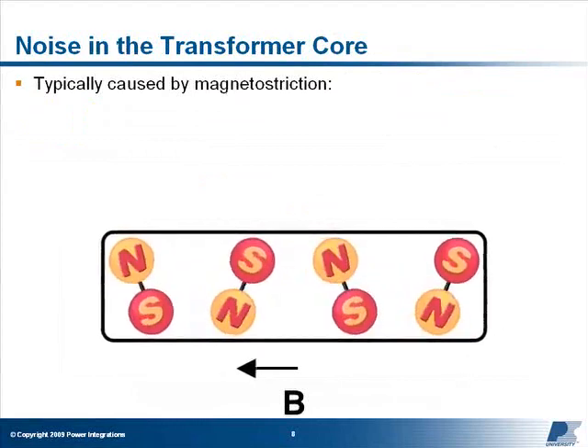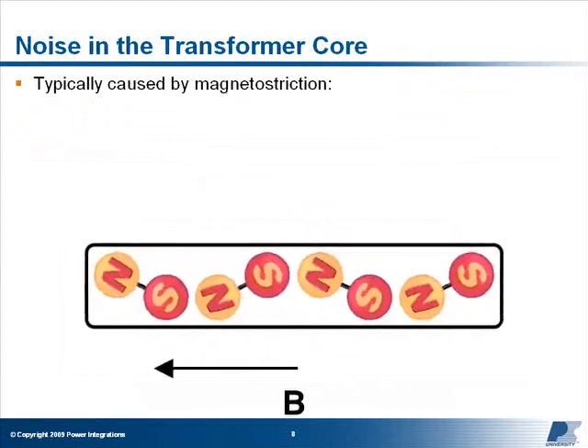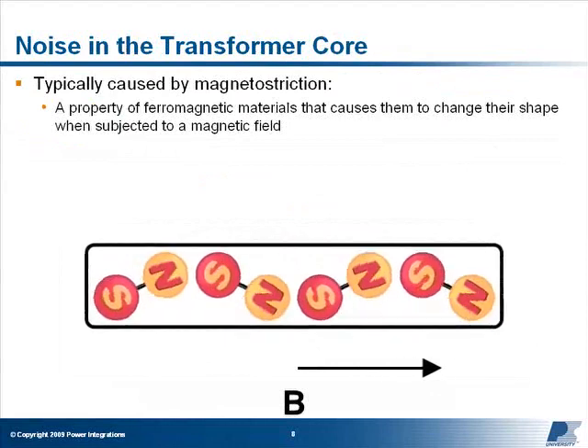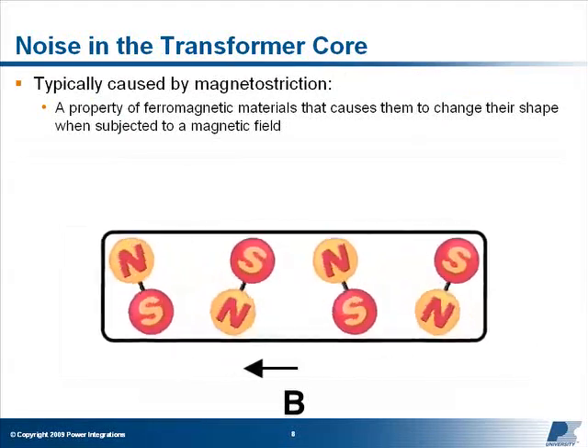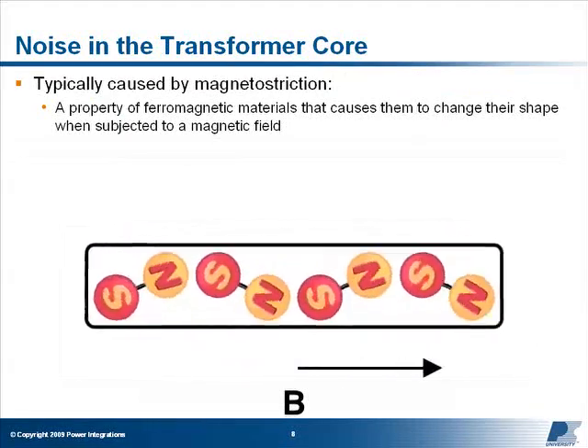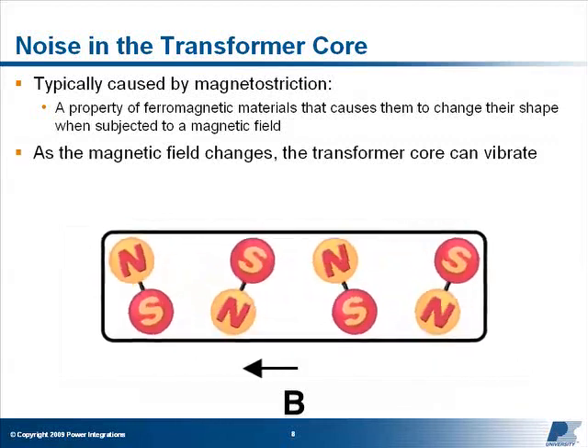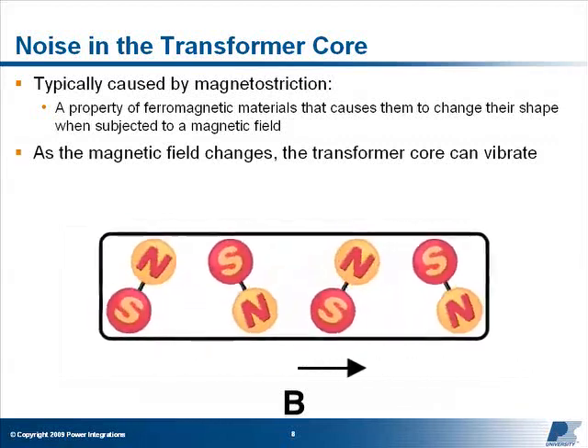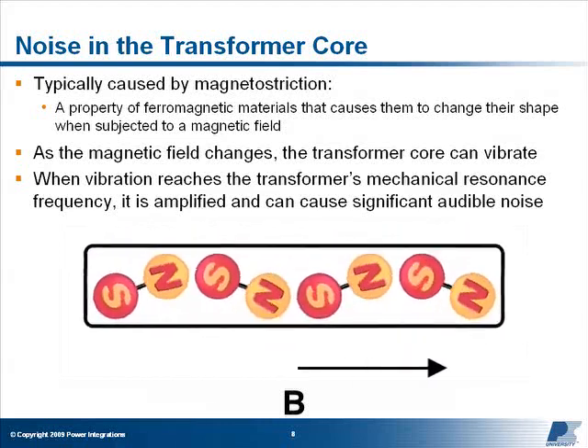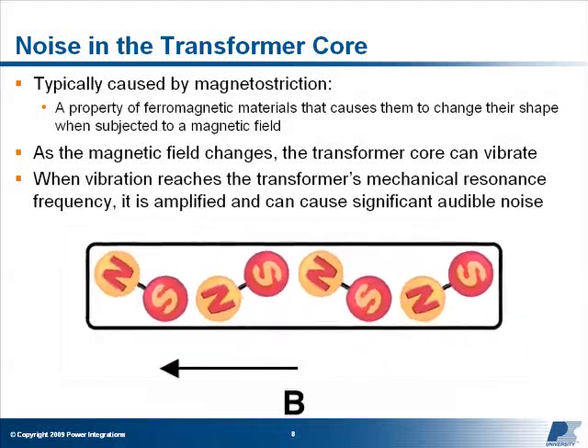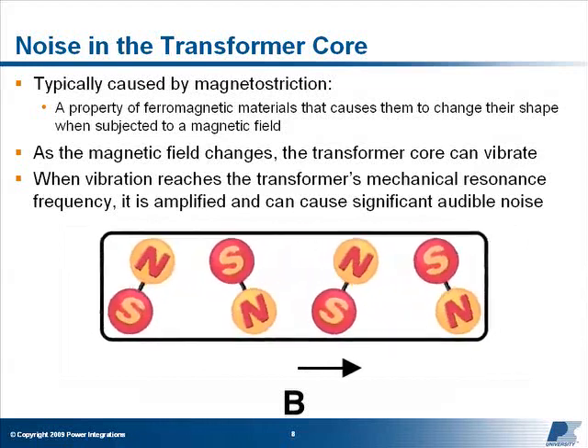Noise generated by transformer cores is caused by a similar effect called magnetostriction. Many ferromagnetic materials change shape when subject to a magnetic field. As the magnetic field changes in the transformer core, this can cause it to physically vibrate. When this vibration reaches the mechanical resonance frequency of the transformer, it will be amplified and may cause large amounts of audible noise.